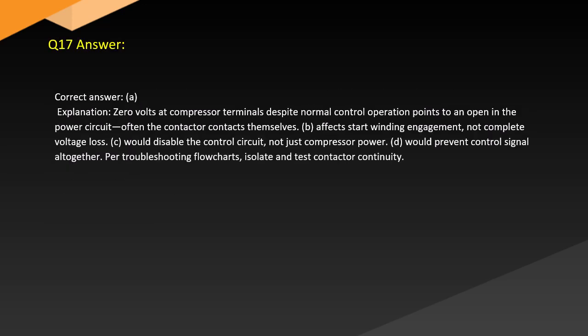Answer. Correct answer: A. Explanation. 0 volts at compressor terminals despite normal control operation points to an open in the power circuit, often the contactor contacts themselves. B. Affects start winding engagement, not complete voltage loss. C. Would disable the control circuit, not just compressor power. D. Would prevent control signal altogether. Per troubleshooting flowcharts, isolate and test contactor continuity.